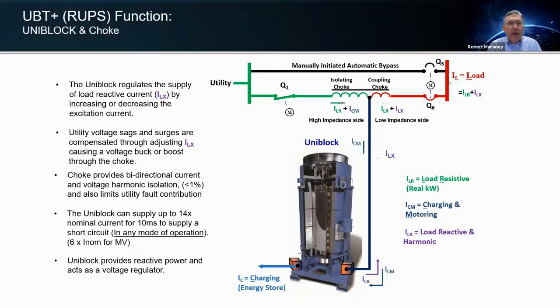And if you look, the uniblock, as I said, can provide 14 times nominal current downstream to help clear downstream faults. In medium voltage, it does come down to around 6 to 8 times that level per the system. But one of the nice benefits is you don't have to deal with going to bypass when you have an instantaneous requirement for inrush on the system. And you'll see where we actually take advantage of that in some of the application notes in a few slides.